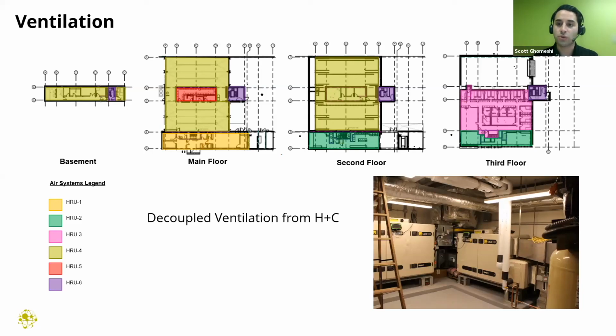The heating and cooling equipment can recirculate and only operate when needed, whereas the ventilation systems operate all the time. That gives us the opportunity to significantly reduce fan energy and the heating and cooling equipment, because it's not needed to run to supplement the ventilation load to those spaces.